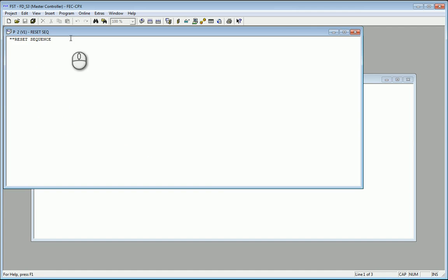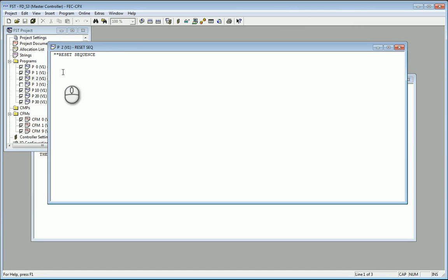Currently we have nothing on it, which is empty. And what we want to do in here is to move the stations, each of the 3 of them, to the initial positions that the coursework tells us that they must be in. Right. So station 2 and station 3 are a little bit easier to do because a lot of their valves are spring return valves. So as soon as they're fired up anyway, they're tracked back to what is deemed to be their safe position, which is fine.